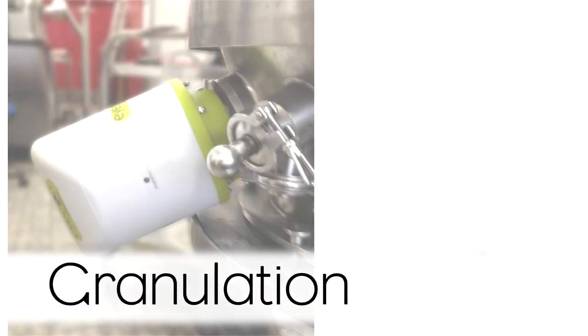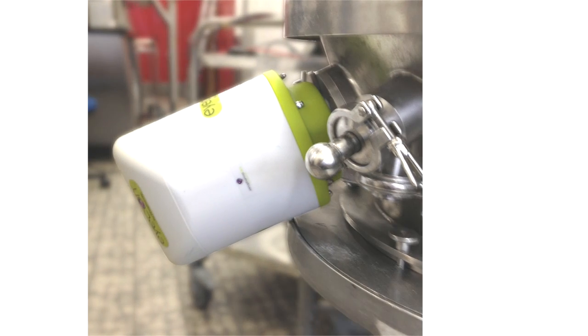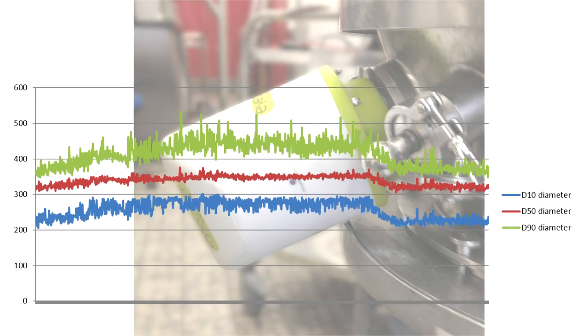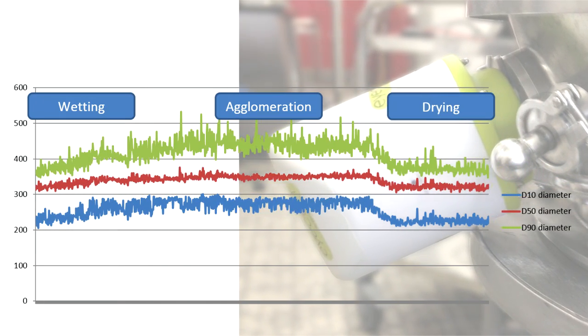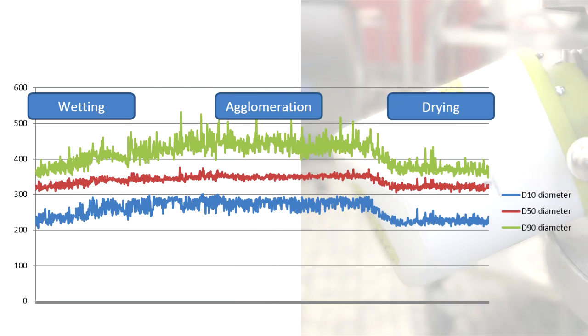The ICON is in use in both industry and academic environments, monitoring and controlling a wide range of particle size sensitive processes. These include fluid bed granulation, where the real-time particle size data is used to ensure that the granulation equipment is operating correctly through the wetting, agglomerating, and drying phases, as well as to detect the process endpoint.